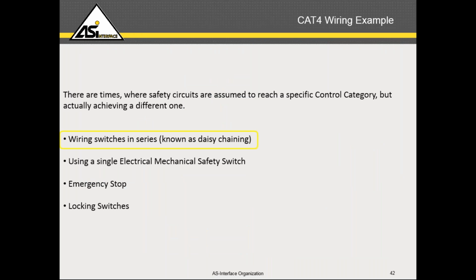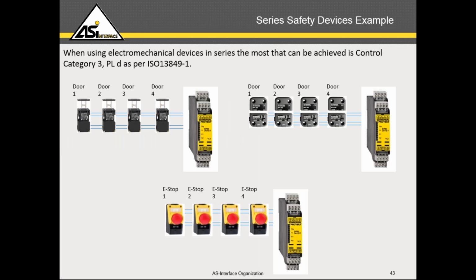But the real problem occurs in real life when we daisy chain these types of interlocking devices, and the circuits are designed with series connection to save wiring cost, or require fewer safety relays, or fewer safety inputs to the safety PLC. The safety designers and machine designers may forget to take fault accumulation into consideration. Sometimes you think that you are achieving the highest you can achieve when you are series connecting these types of door interlocks or emergency stops.